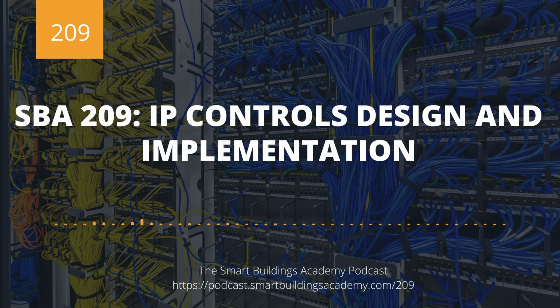If they are going to be upgrading network gear in their IDF or MDF or bringing stuff down for maintenance, you need to know that, because that can affect, let's say you're in a hospital and you have an IP controller, and that IP controller for that hospital is feeding back information to another IP controller on an air handler to go and then drive that air handler appropriately. Well, if the switch gear comes down for some maintenance, that could then take down control of that operating room. And so it's really important that you have a conversation about SLAs. That's basically the guarantee for your network being up, called a service level agreement, by the way.